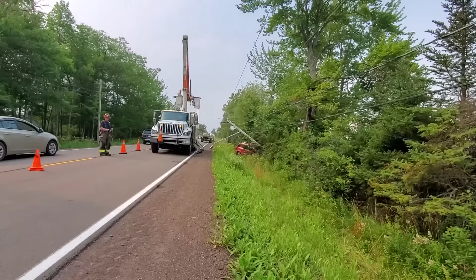The lead feeding the cutout had quite a bit of pressure on the crossarm itself. A dry wooden pole isn't an excellent conductor, so it wasn't enough to draw enough current to pop that again. But technically that pole would be considered energized. The voltage would dissipate fairly quickly through the pole, but in a circumstance like this, I would absolutely not touch that vehicle or that pole, or go near it, until the line is opened, the potential is checked, and grounds are installed.